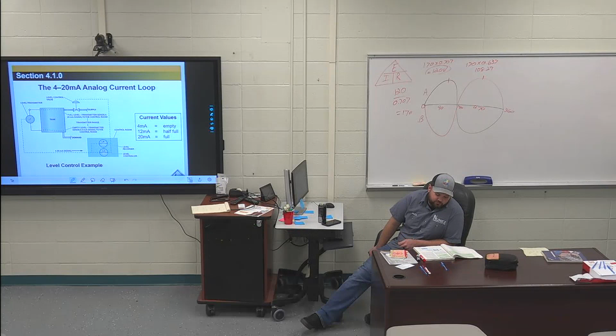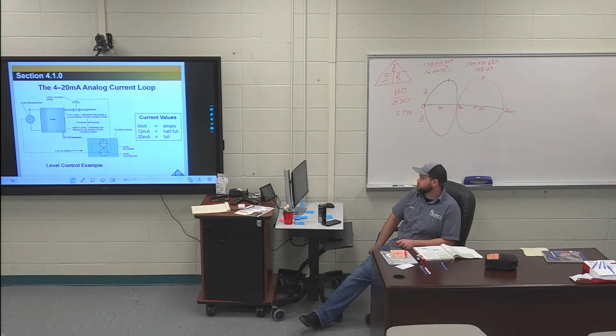On that process control train out there, I've got 10 inches, 0 inches, and 5 inches for my analog signal. So I have a pressure transducer right here, and at the top I have ultrasonic. Both of those will give off a 4 to 20 milliamp signal based on the level of water. So all that's saying is the analog signal varies proportionally with the magnitude of change.